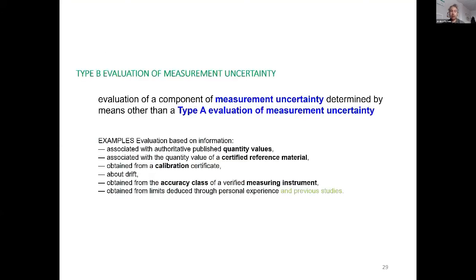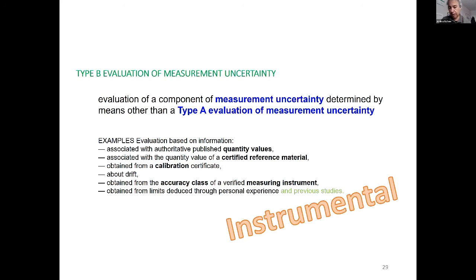We will now go a little bit more into the differences and different types of uncertainty. Consider again that the new GUM is a little bit surpassing this separation, because the more we know of a phenomenon, maybe we are able to move some part of the statistical. Maybe it was noise, it was statistic only, but with a better instrument, we are able to reduce the type A and understand it was a type B, or vice versa. We have more fluctuations, which we suppose it was in the instruments, and it's just statistical something. So they can be partially linked one to the other. The type B can derive from really a number of aspects, which we will see a little bit later on. But basically, they are instrumental and measurement method.